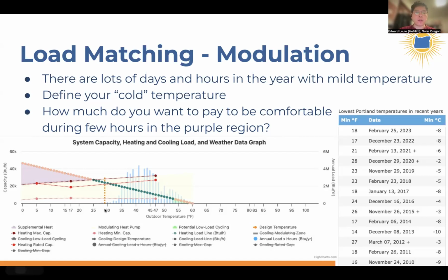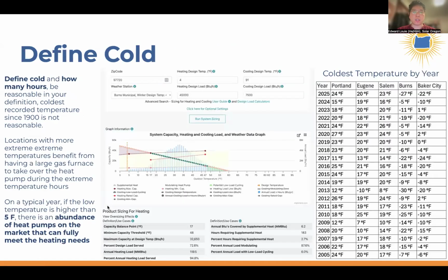Now, for Portland, the design temperature, which is this vertical bar here, represents, looking at a typical year, the value that 99.6 percent of the hours in the year are warmer than. And as you can see, that makes sense. There's barely a blip of the blue bar to the left of this vertical line. So if you want a heating system to cover 99.6% of the times in a year so that you're comfortable, then you want the heat pump to be able to cover that, as we'll look at in the next slide.